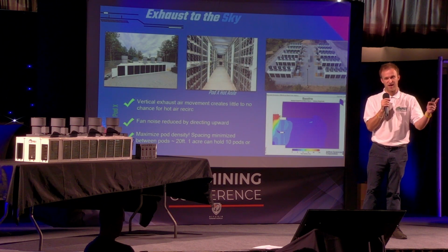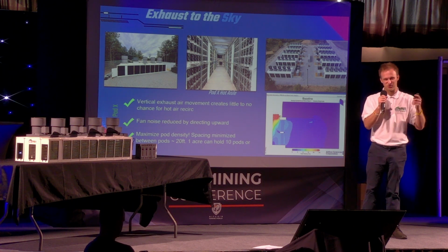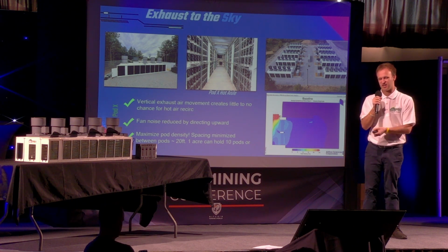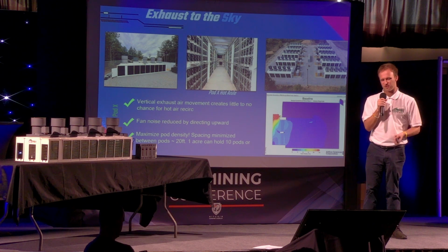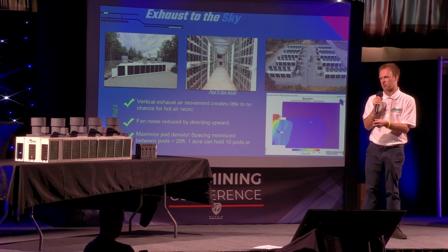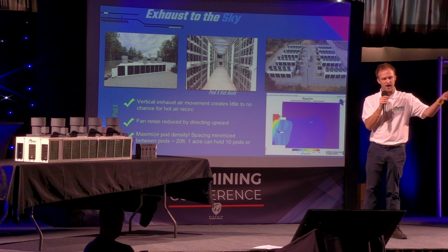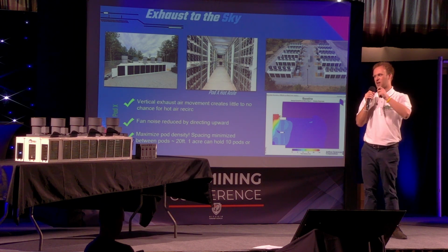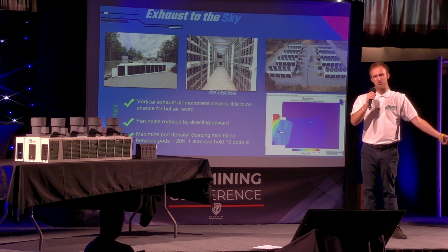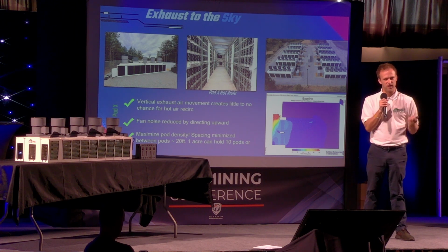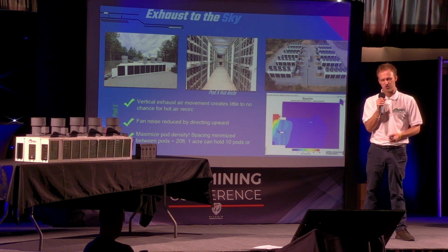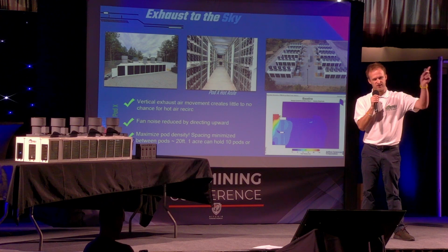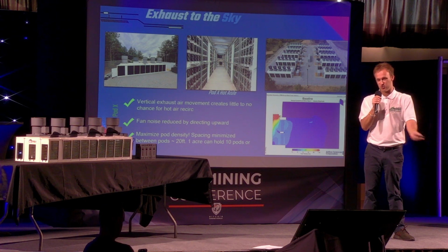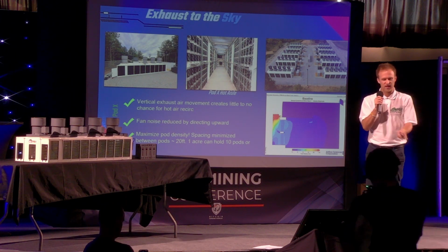So we exhaust to the sky, which is obviously a different solution than going streamlined. You might see this a lot in buildings, but we're a lot more confined to buildings. And this really helps to limit and actually get rid of that hot air recirculation I talked about, because hot air wants to rise, so we're just letting it do that. And by keeping our negative pressure and velocity low in our intake, there's really little to no chance of hot air recirc, so we can run our pods and miners at much higher temperatures. Also, because we're pointing our fans to the sky, the noise is significantly reduced, which I'll go into later. And we can maximize our pod density.